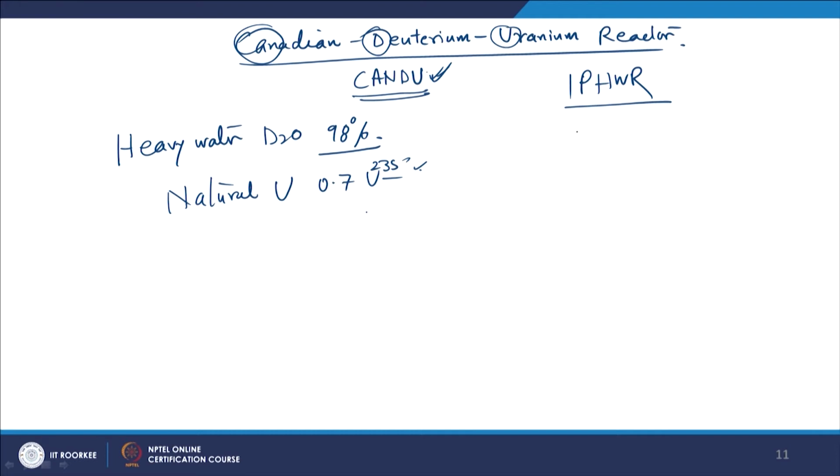It differs from the light water reactor. There are a number of light water reactors, in which the water, H2O, works as a coolant. Here it differs in that manner only, and the heavy water is used as a coolant. But the beauty of this reactor is that only the coolant has to be pressurized, not the entire reactor. So, in case of any accident, in case of LOCA, the severity of the damage is very less.